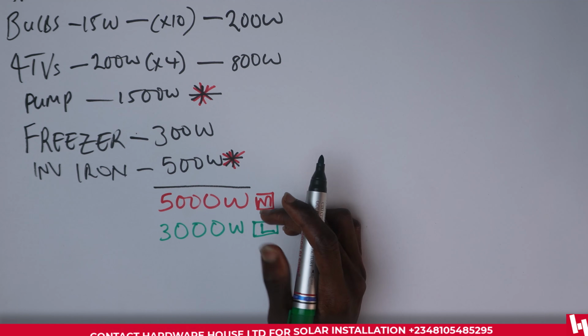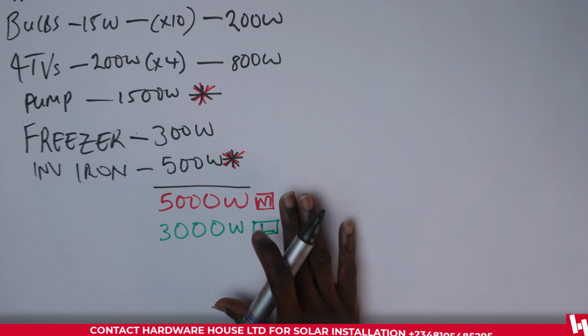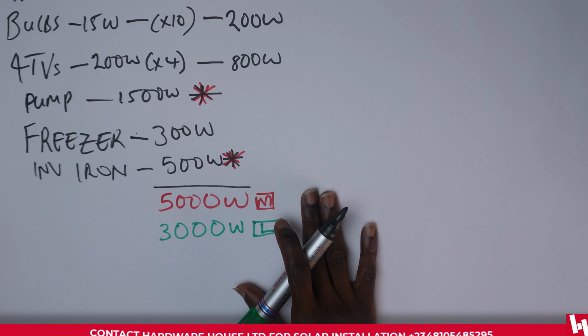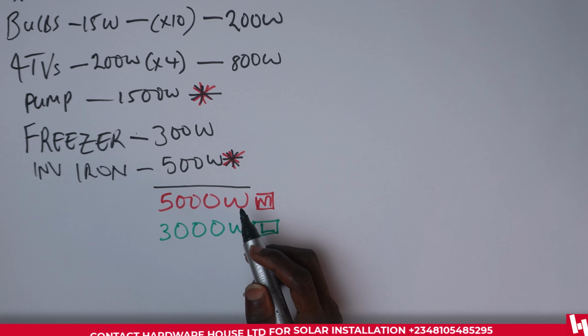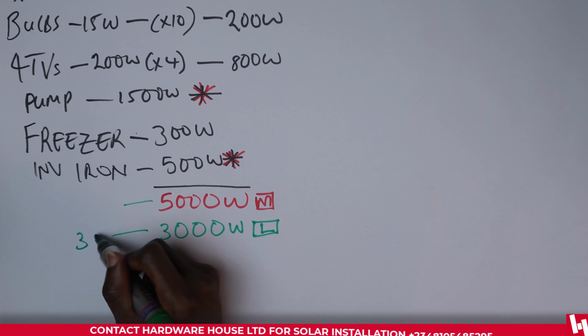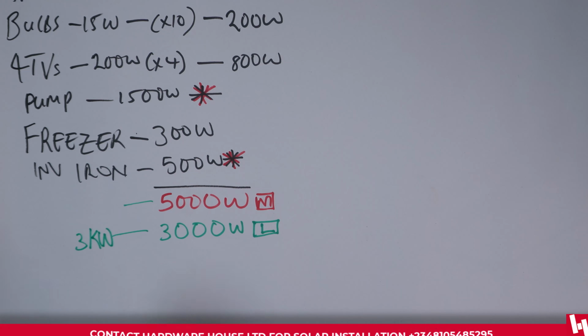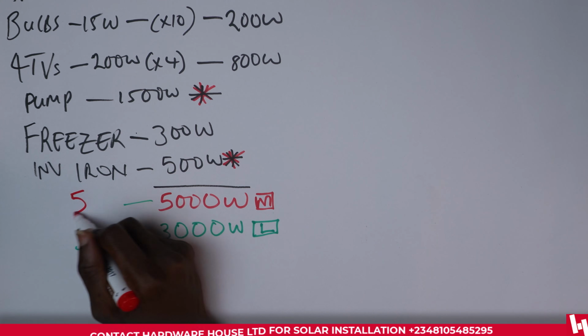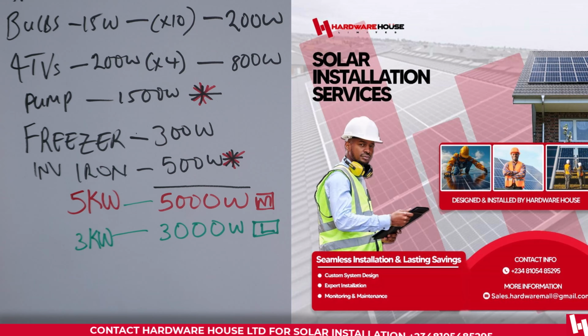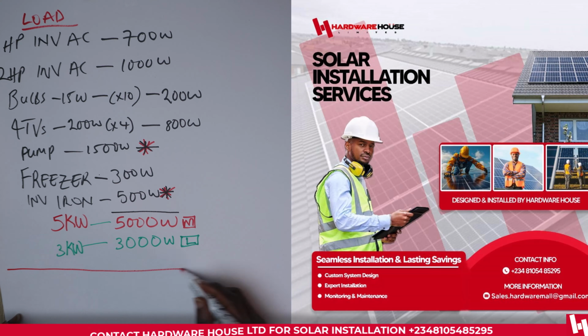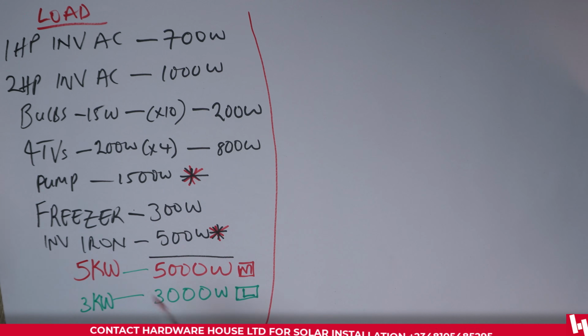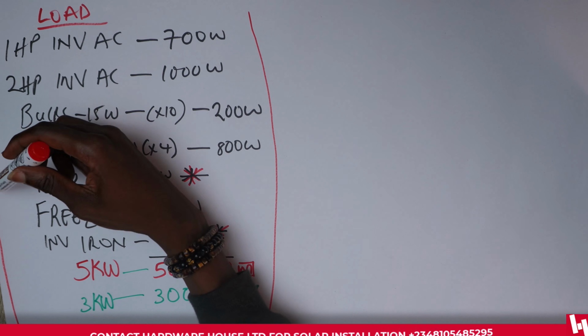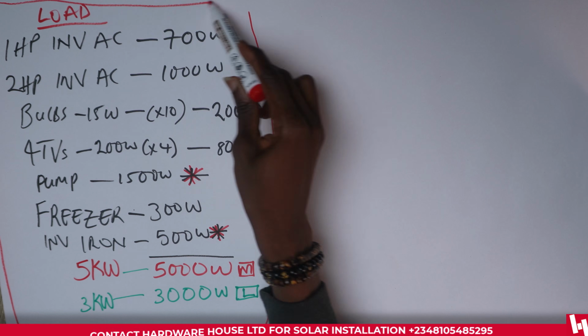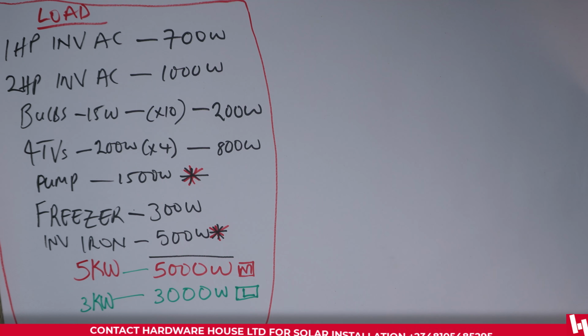So let's convert these two figures to kilowatts because our inverter system is rated in kilowatt and kVA. So we have here 3 kilowatts for the light load and 5 kilowatts for the maximum load. So like we've explained in subsequent videos, once you get the calculation of the house, the next thing we proceeded to do was to calculate the inverter that we were going to get for this client.